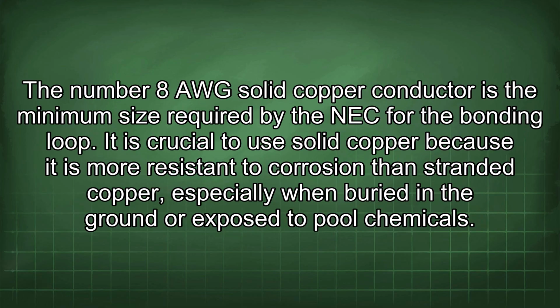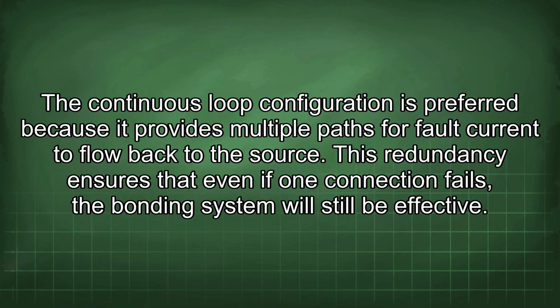The number 8 AWG solid copper conductor is the minimum size required by the NEC for the bonding loop. It is crucial to use solid copper because it is more resistant to corrosion than stranded copper, especially when buried in the ground or exposed to pool chemicals. The continuous loop configuration is preferred because it provides multiple paths for fault current to flow back to the source. This redundancy ensures that even if one connection fails, the bonding system will still be effective.